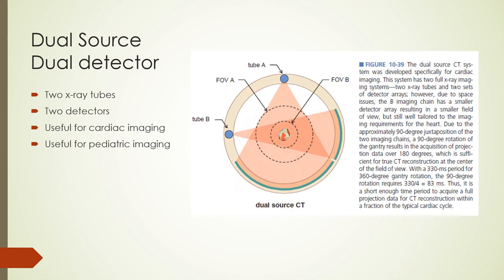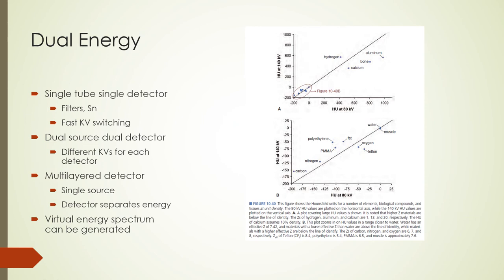The desire to image fast-moving structures like the heart led to the development of dual source and dual detector CT scanners. In dual source CT, the gantry has two X-ray tubes and two detectors at 90 degrees to each other, cutting rotation time in half compared to a single tube and detector system. In some machines, one tube is primary and the other secondary, with the secondary having a smaller generator and smaller detector. Dual source systems are particularly used for cardiac imaging and pediatric patients because of fast rotation times.